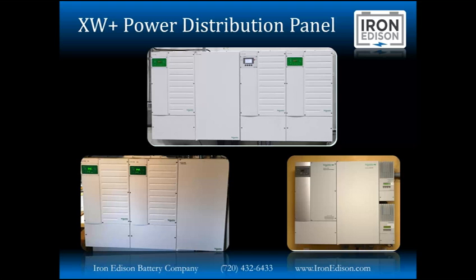Later they realized they needed to upgrade their infrastructure to three-phase. So we added 2 additional inverters and reprogrammed them. Instead of doing split phase, they're all now doing a 208 three-phase output. As you can see, you can mount the inverters on either the left side or the right side of the power distribution panel.